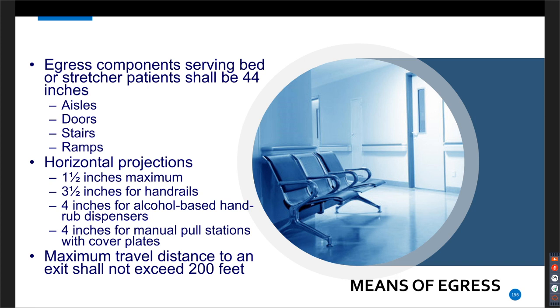So you'll see requirements in 10 that are general, and then you keep reading. You do, when you read code, right, you keep reading. And there are some specifics for the I2s, 2-1s. So the horizontal projections are limited to 1.5 inches, but you could have 3.5-inch projections for handrails. And then for the alcohol-based hand rub dispensers, those can project 4 inches, and pull stations can project 4 inches.